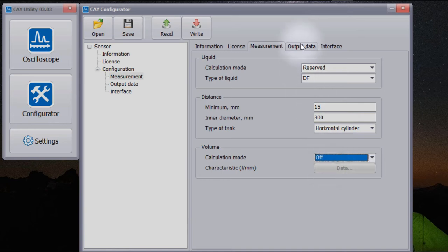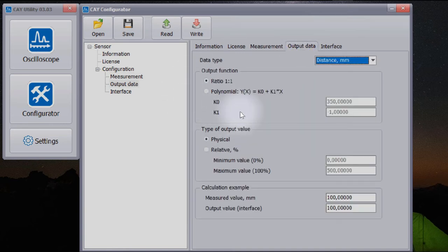We can also set further signal calibration or scaling. For example, we want to know not the level height, but the distance between the tank cover and the liquid. In this case, we can recalculate it there. In the calculation example, we can see a preview of results. If the sensor measures a 100 mm level, we will receive a 200 mm distance between the tank cover and the liquid level, and this value will be the sensor output. Also, we can set up the sensor output to show the relative level of volume in percent. With a maximum 300 mm level, a measured 130 mm will give us 43%.